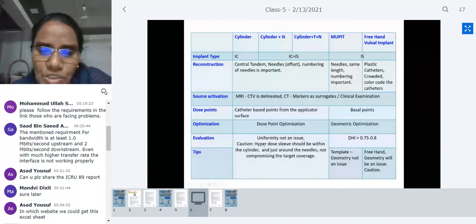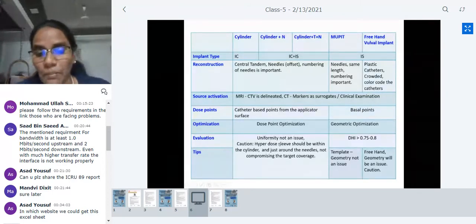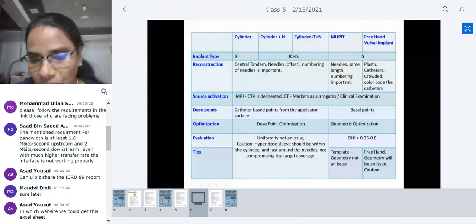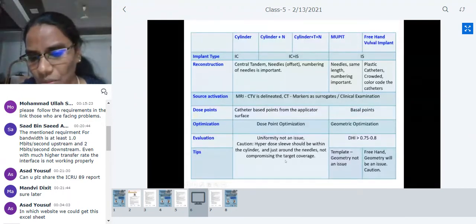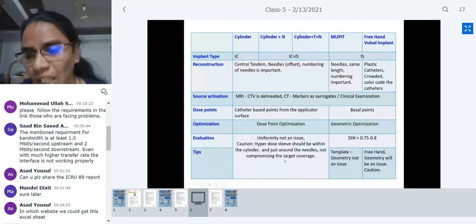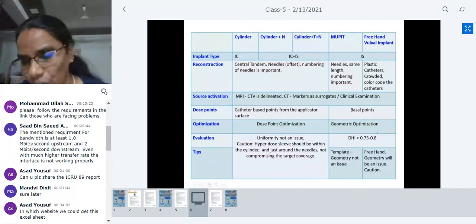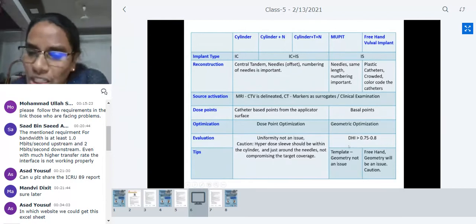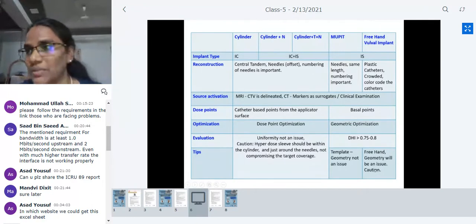When you're using these kinds of implants, the cylinder or cylinder plus needles or tandem, the uniformity is not an issue, but be careful that your hyperdose sleeve should be within the cylinder and it should be just around the needles. And what does this mean? We will see that now. And here, you also have to keep in mind that your dose homogeneity index must be more than 0.75. And if it is going to be a template-based implant, the geometry may not be an issue. But if it's going to be a freehand implant, then geometry must be very important. Otherwise, you will end up having huge hotspots.